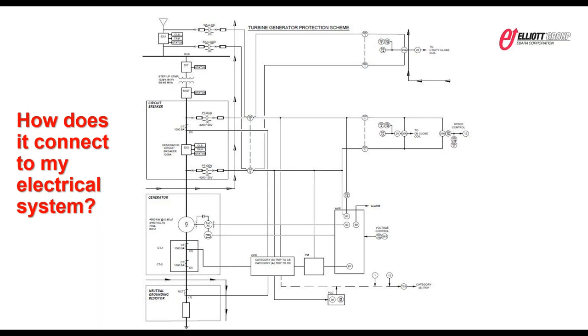You can see here, on the steam side, you have pressure and temperature monitoring. The control system is going to be looking at pressure set points, or ultimately trying to control the speed of the turbine. But on the electrical side, you're going to have inputs from PTs and CTs, things off the generator, that are looking at current and voltage, and those signals are going to go into protective relays so that if you have a case where it's an overcurrent or something like reverse power, it's going to send a signal to those protection relays and open up the breaker, disconnecting this generator.